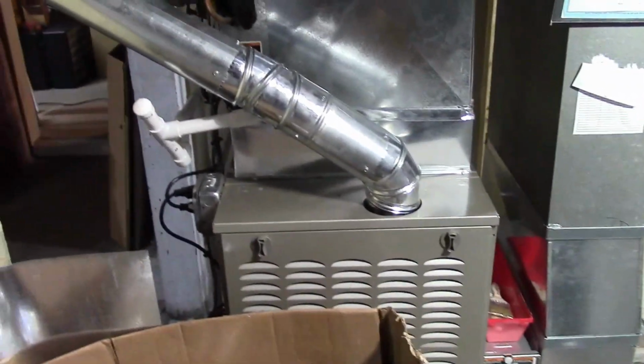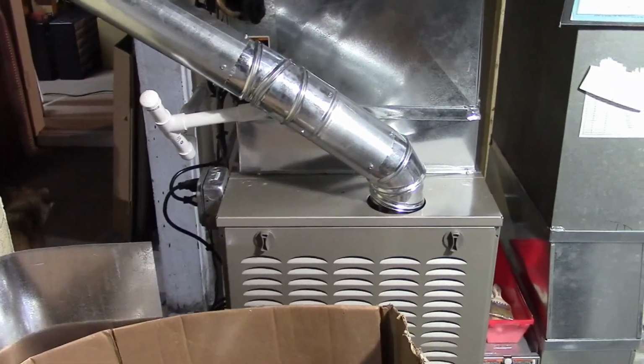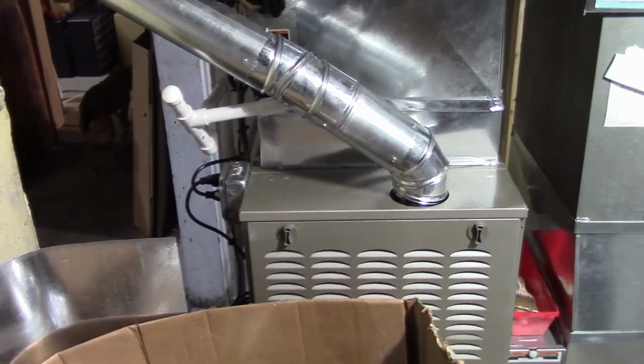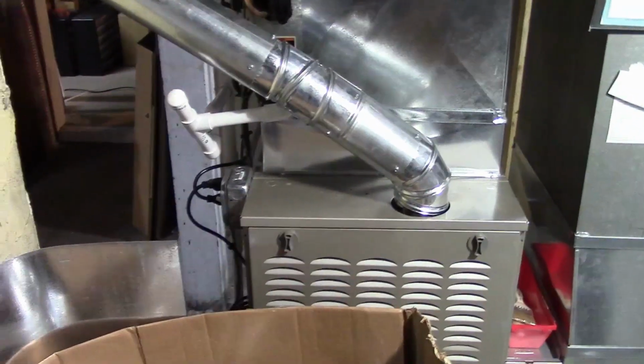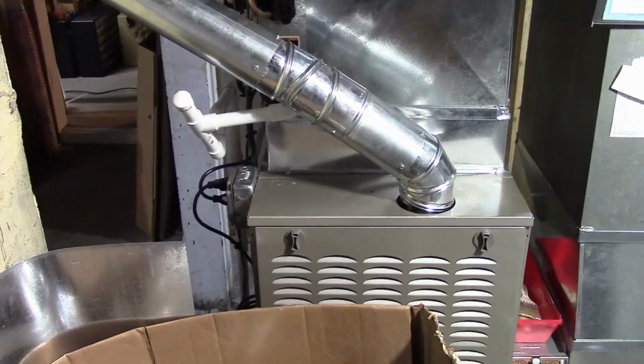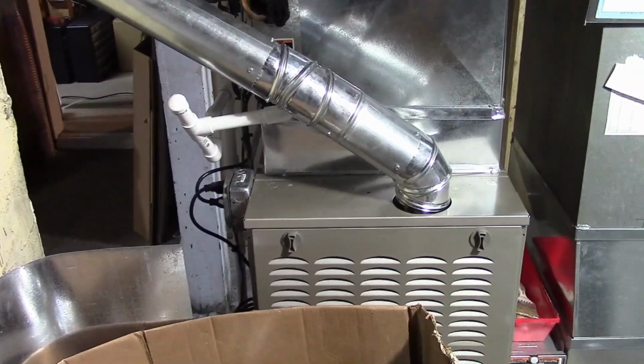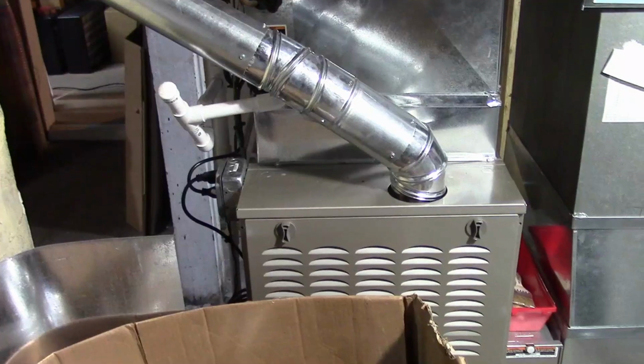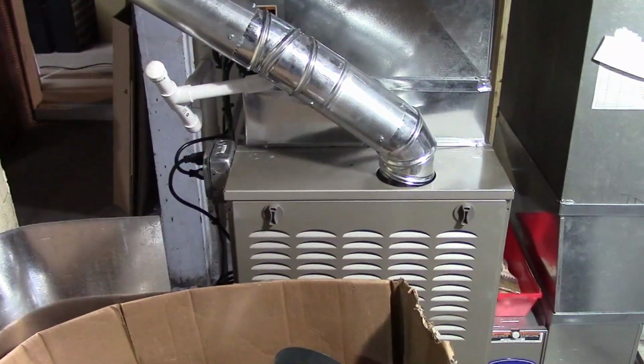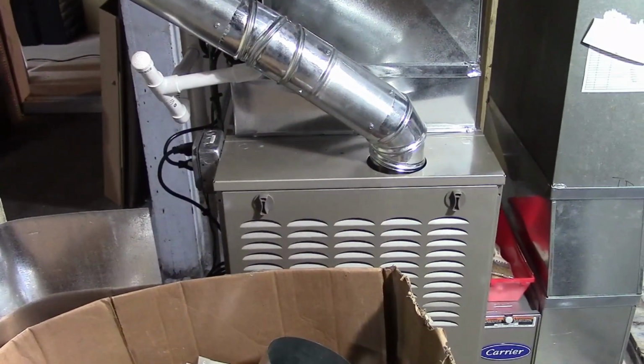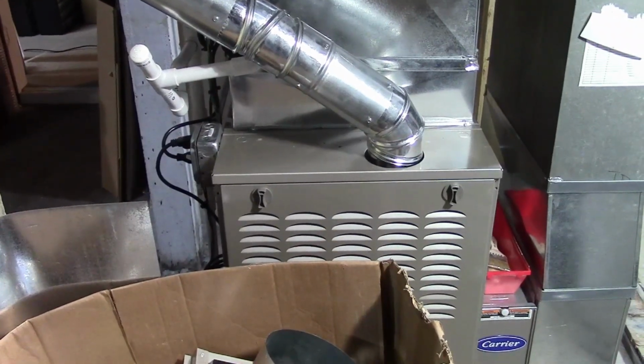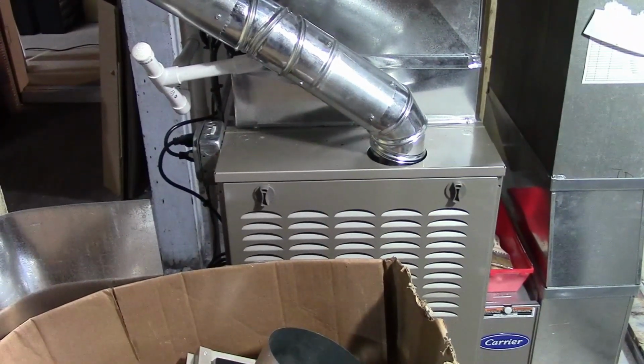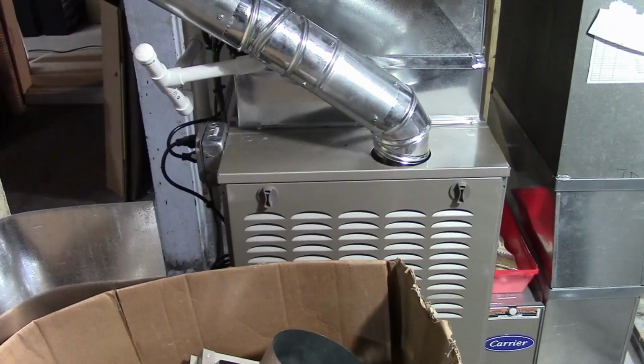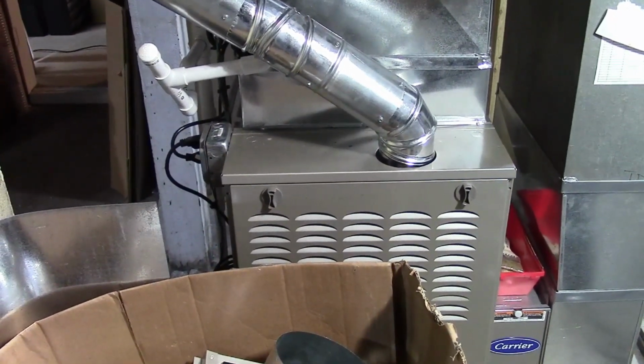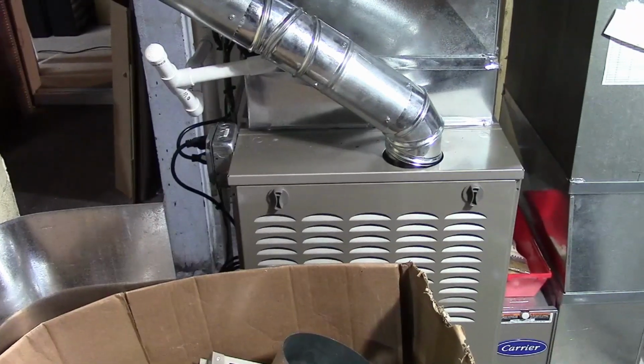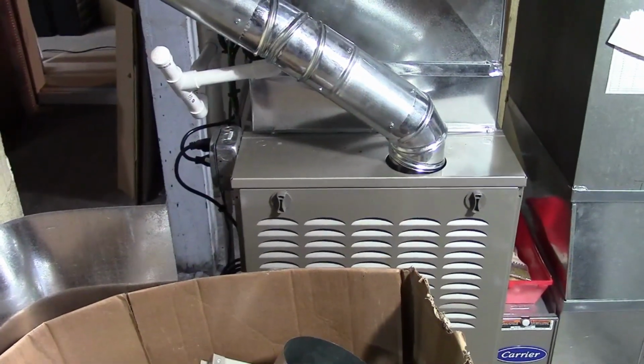I got a lot of comments about the pros and cons of different systems and why didn't we go with a more efficient system. Cost, it comes down to that. Between an 80% efficiency basic system with the right number of BTUs, about 90,000 I think we got, versus like a 98% efficient system, it was like $5,000 plus additional maintenance costs plus a shorter life, more things to go wrong, more complex.